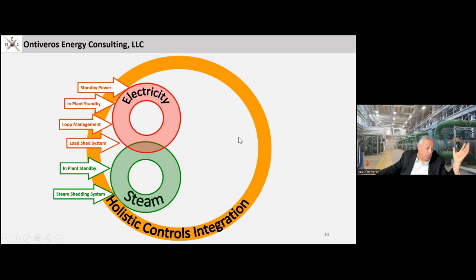You also want to have a steam shedding system. If my steam turbine trips on campus, that's 400,000 pounds per hour at peak load at 25 megawatts. It's a 400,000 pound steam load I have too much of. So we have a quench vessel that allows us to shed it. If I have an upset, it allows me to stabilize things. My controls manage all that, and I can then fix it and get it back online if I need to.